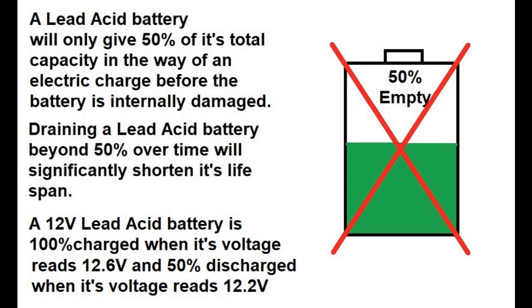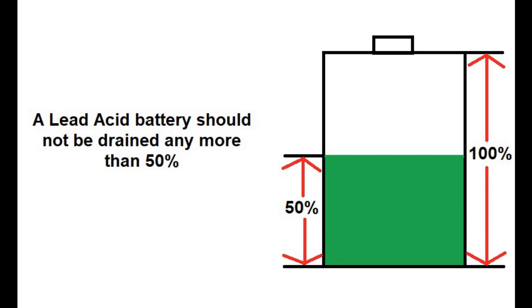Pro 2. This is often the deal maker. A lead-acid battery should not be discharged to less than 50% of its capacity, or you might deteriorate its internal workings. Therefore, a 12-volt 100 amp hour lead-acid battery only really works out to be a 50 amp hour lead-acid battery. You're only really getting half the advertised power capacity in a lead-acid battery.